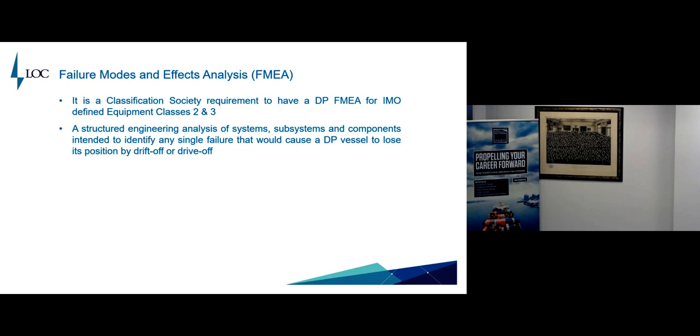The important thing is that, as per the worst case failure design, the surviving group should not be affected by the other group; it should be independent. That process is called FMEA. The FMEA does the first analysis, and then based on the analysis, it develops a test program called the proving trials.